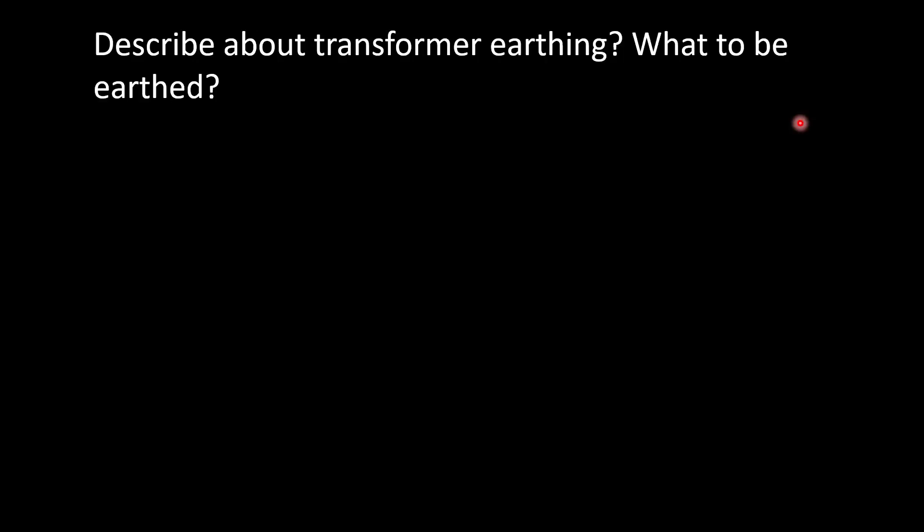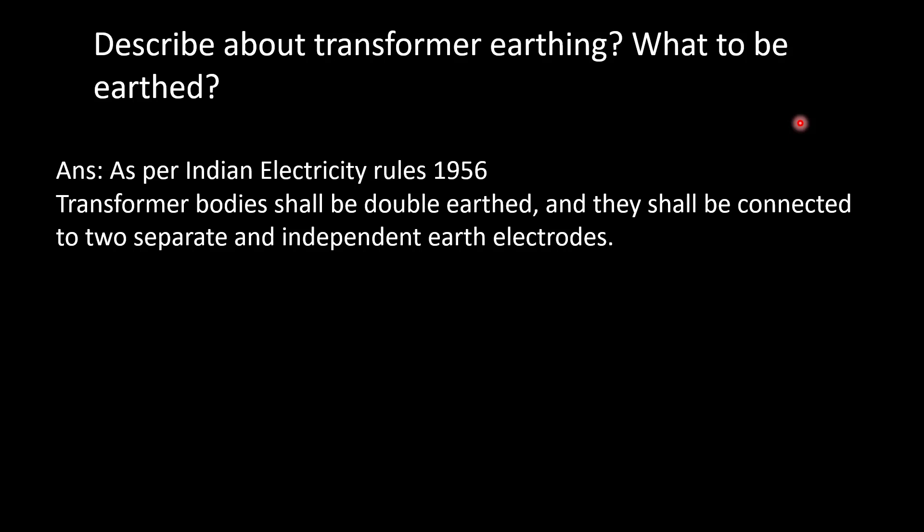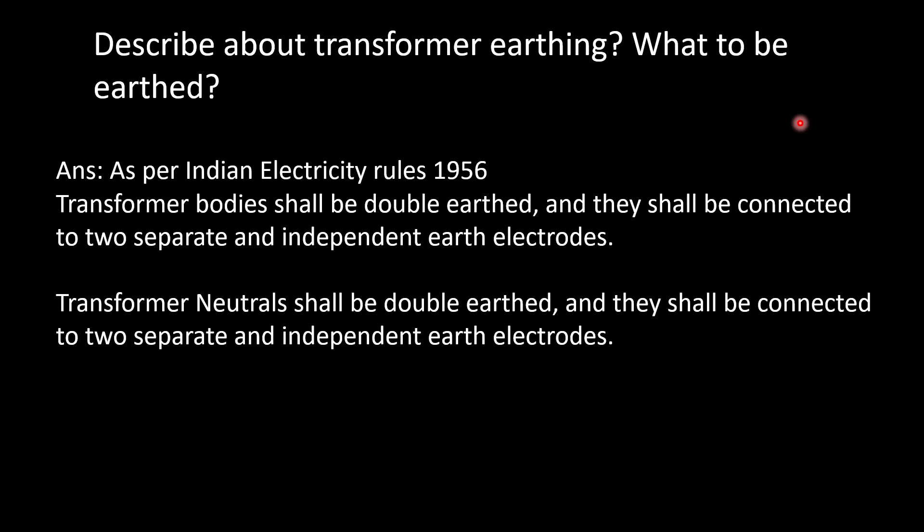Describe transformer earthing and what needs to be earthed. As per Indian Electricity Rules 1956, transformer bodies shall be double earthed and connected to two separate and independent earth electrodes. Transformer neutrals shall also be double earthed and connected to two separate and independent earth electrodes. So for a single transformer, there are four earth pits — two for the body and two for the neutral.